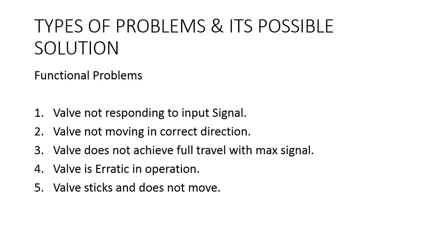Input signal to the actuator may not be correct, so you can try to reverse the signal output, the system output signal, maintaining the safety requirements. By this we can rectify this problem.